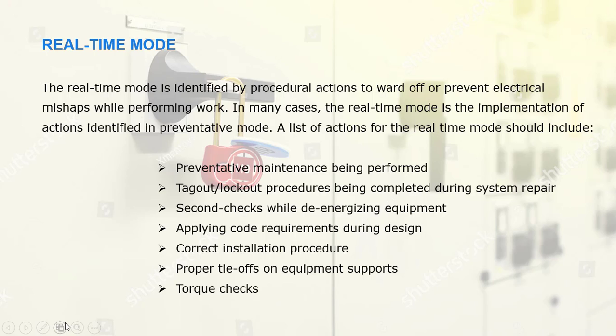Real-time mode. The real-time mode is identified by procedural action to ward off or prevent electrical mishaps while performing work. In many cases, the real-time mode is the implementation of actions identified in preventative mode. A list of actions for the real-time mode should include preventive maintenance being performed, lockout-tagout procedures being completed during system repair, second checks while de-energizing equipment, applying code requirements during design, correct installation procedures, proper tie-offs on equipment supports, torque checks.